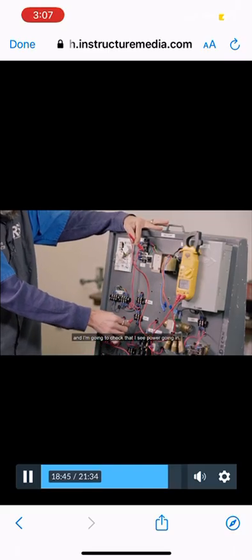So we had a problem earlier where we didn't have any power coming out of here. This one, it's coming out, which means my high pressure switch is okay. It's closed. So I'm going to move down to the low pressure switch, and I'm going to check that. I see power going in. That's a good sign. But no power coming out the other side.